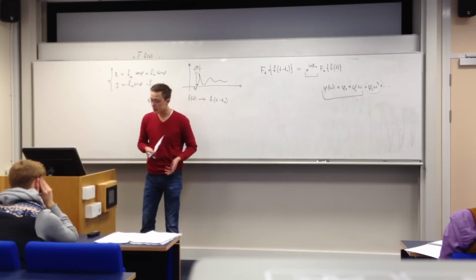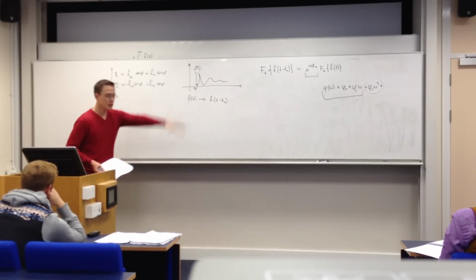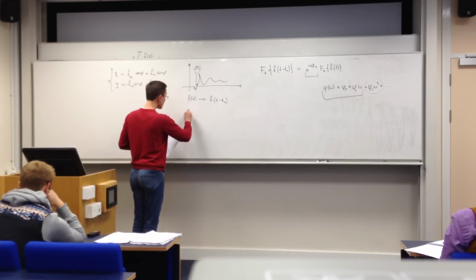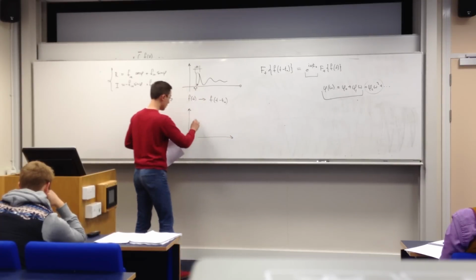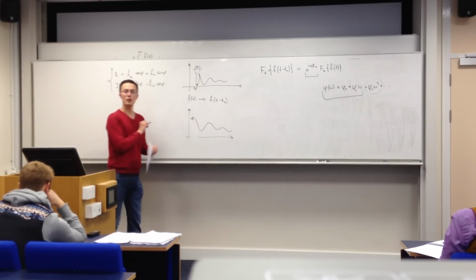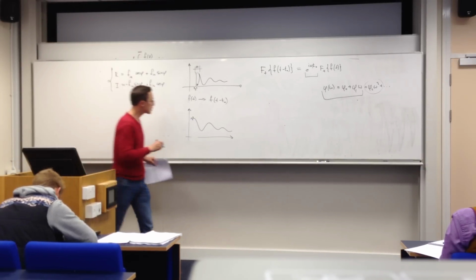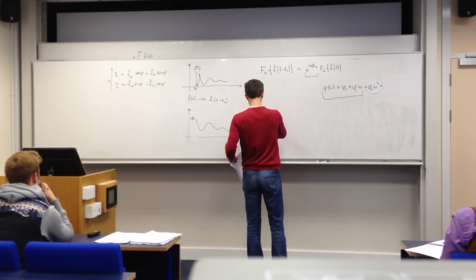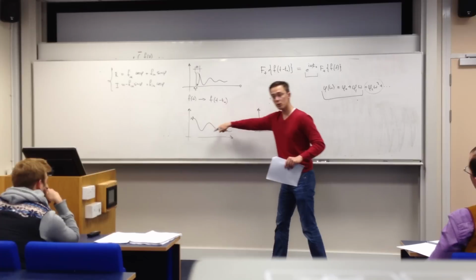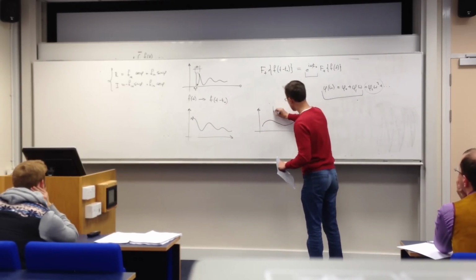Alternatively, if the probe is old, some capacitors will be arcing in it. Alternatively, if the cabling is not selected well, there will be some radio frequency sloshing to and fro in there. Anyway, the basic result is that when you're recording your FID, it looks reasonably well, but it will have a few initial spikes in it. The common result, if you just Fourier transform this signal, is that you will have your spectrum, because the narrow lines are determined by the long-term behavior of the FID, but the baseline would look like this.